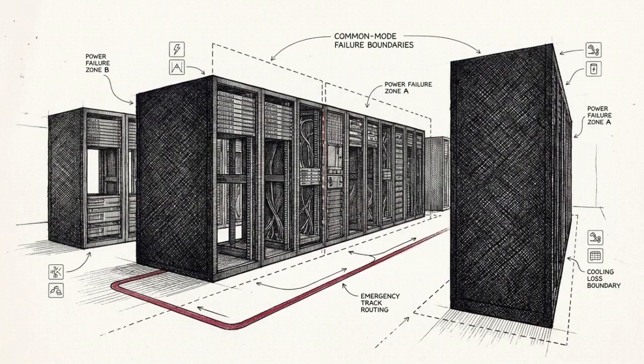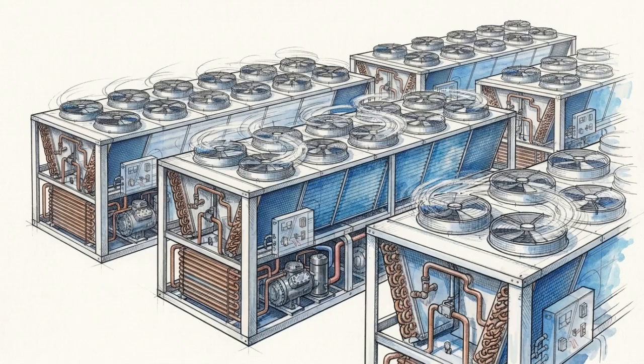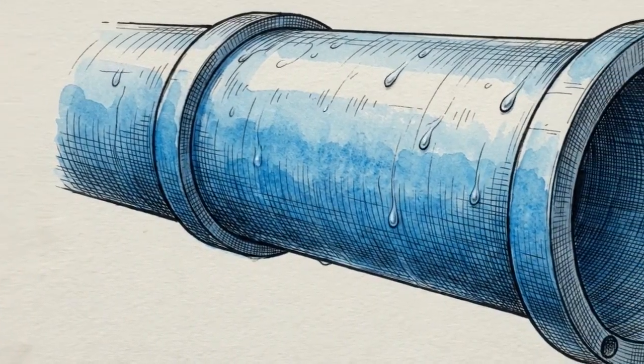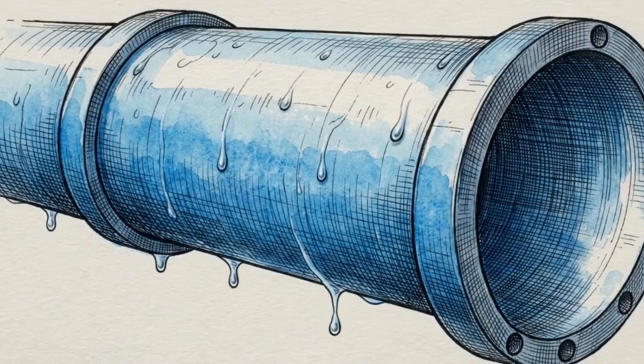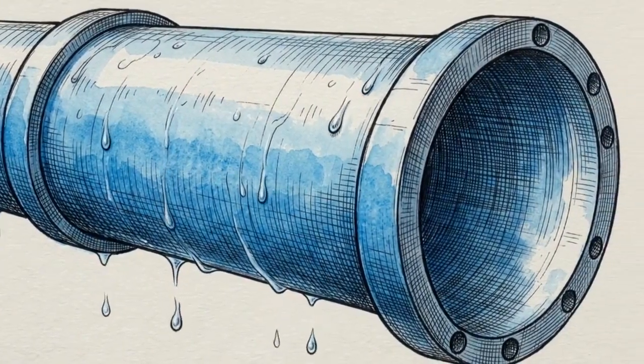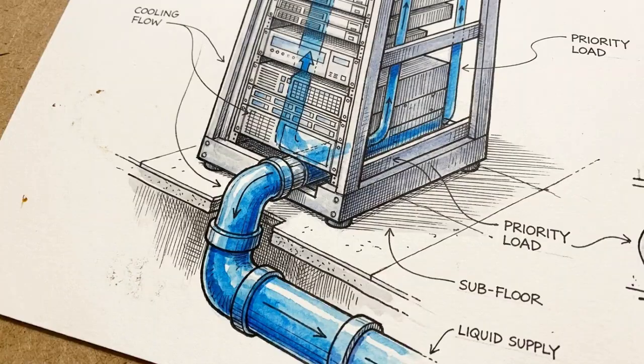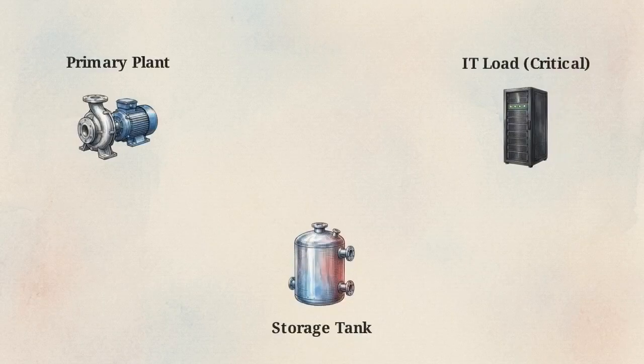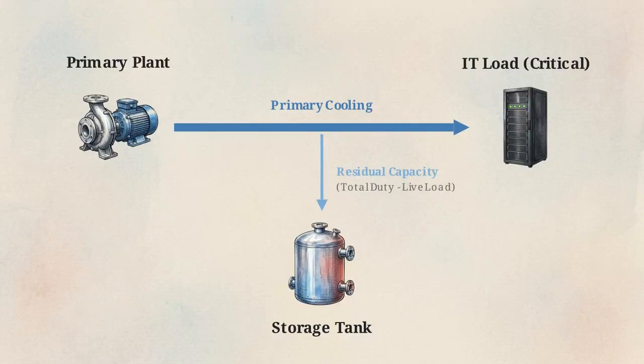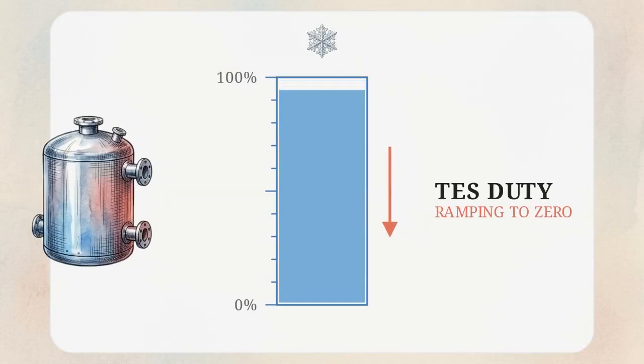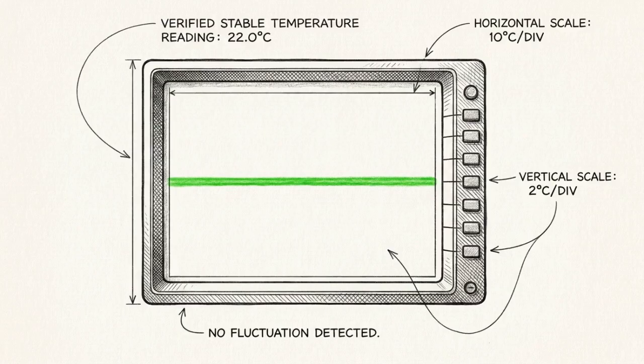Once primary power is restored, the facility enters the recovery state. The system must transition from the stored energy back to the primary chillers smoothly, without inducing a hydraulic shock. During this phase, the critical IT load is always served first. The storage tank is strictly recharged using only the verified residual cooling capacity left over from the primary plant. This requires a bumpless return logic. The controller ramps the thermal storage duty down to 0 while continuously verifying the new chiller supply temperature is stable.